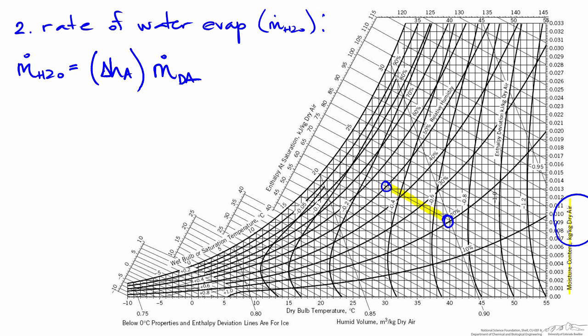Now we don't know what the flow rate of dry air is. We were given a volumetric flow rate. There's another quantity on the chart that's going to help us, and that's the humid volume. This is in units of cubic meters of humid air per kilogram of dry air. So by looking at the units, if we want the mass flow rate of dry air, we need to divide the volumetric flow rate by the humid volume. So we need to find the absolute humidity at the inlet and the outlet as well as the humid volume.